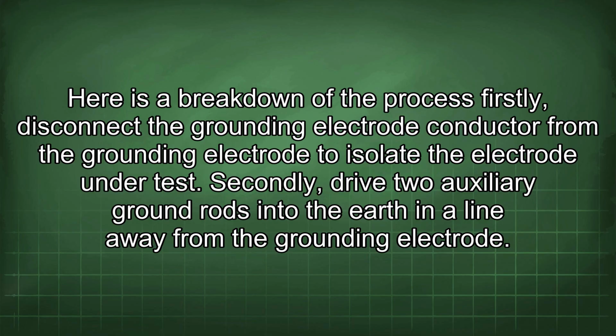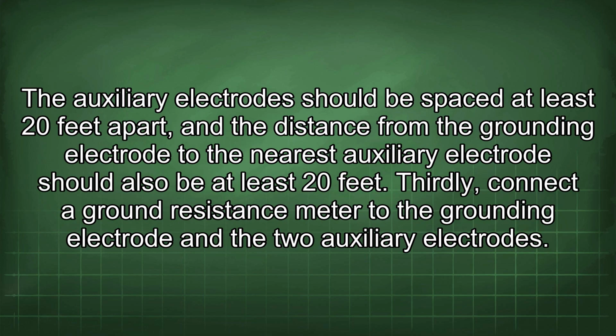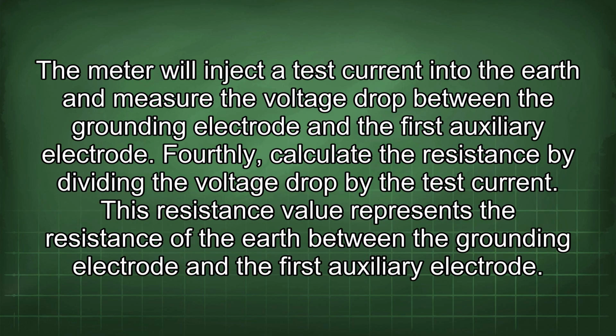Firstly, disconnect the grounding electrode conductor from the grounding electrode to isolate the electrode under test. Secondly, drive 2 auxiliary ground rods into the earth in a line away from the grounding electrode. The auxiliary electrodes should be spaced at least 20 feet apart, and the distance from the grounding electrode to the nearest auxiliary electrode should also be at least 20 feet. Thirdly, connect a ground resistance meter to the grounding electrode and the 2 auxiliary electrodes. The meter will inject a test current into the earth and measure the voltage drop between the grounding electrode and the first auxiliary electrode. Fourthly, calculate the resistance by dividing the voltage drop by the test current.